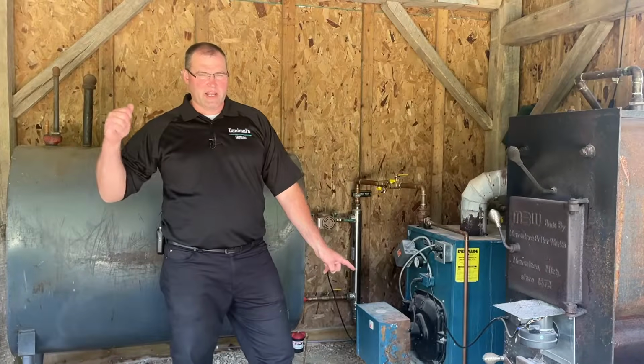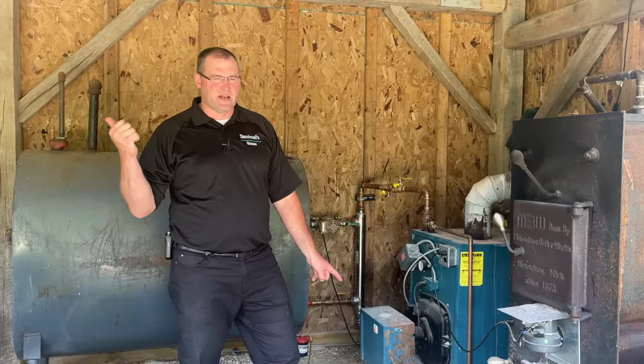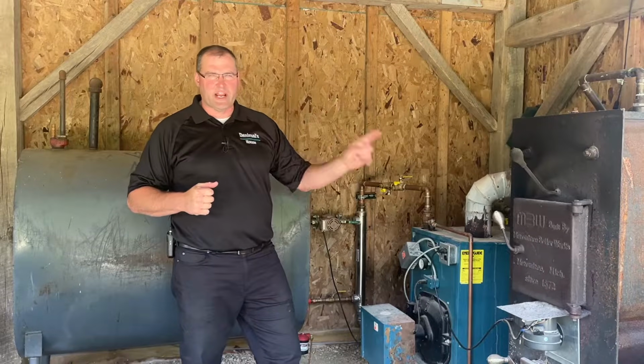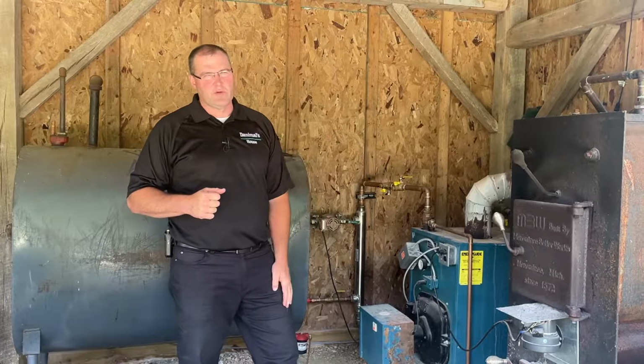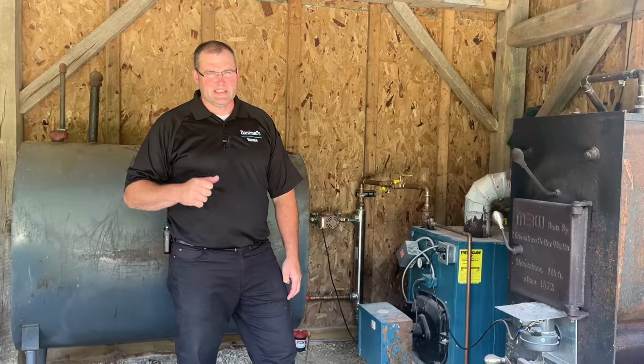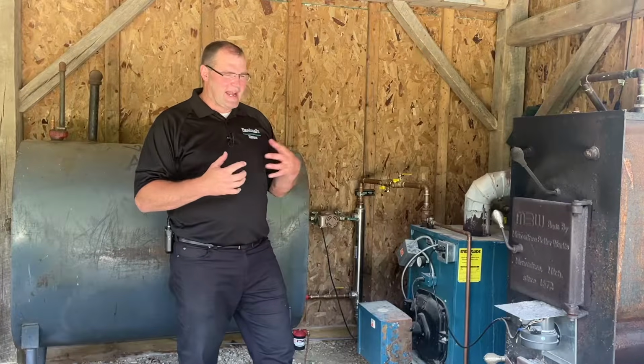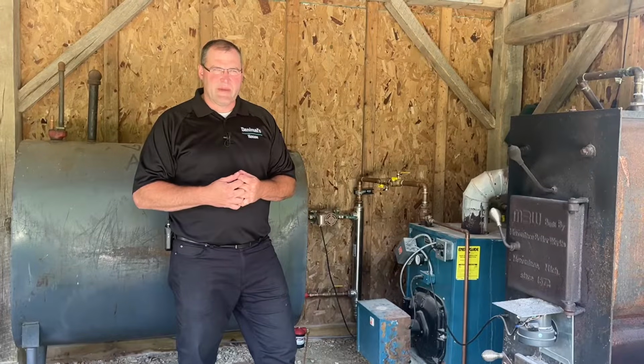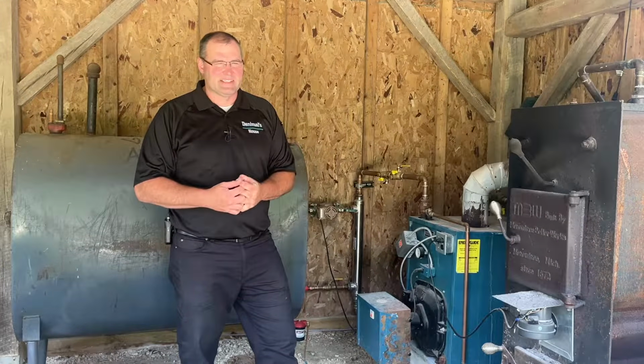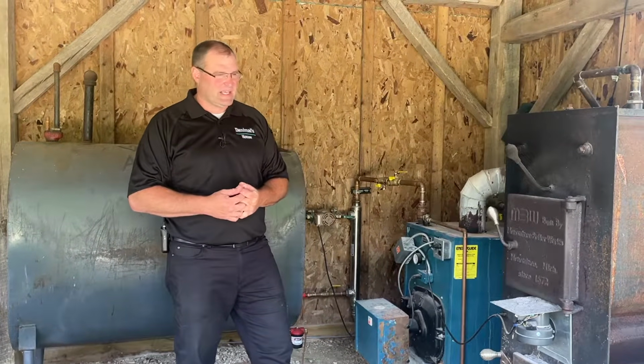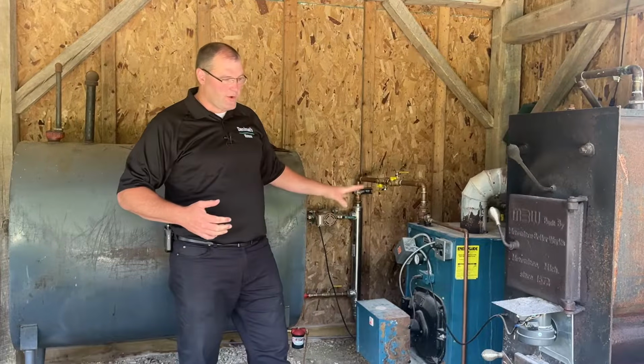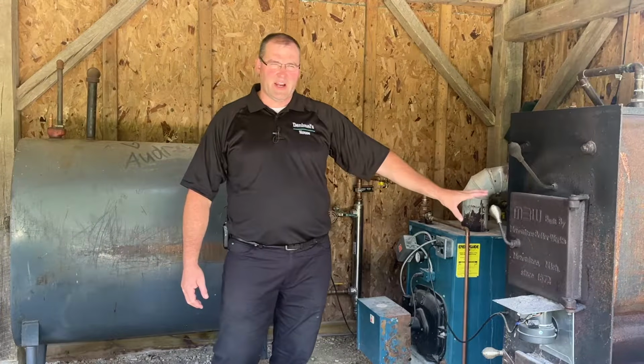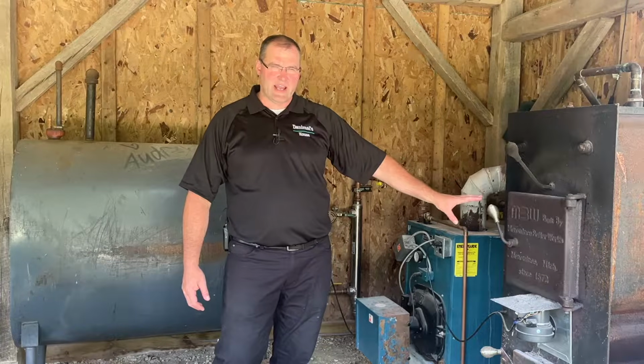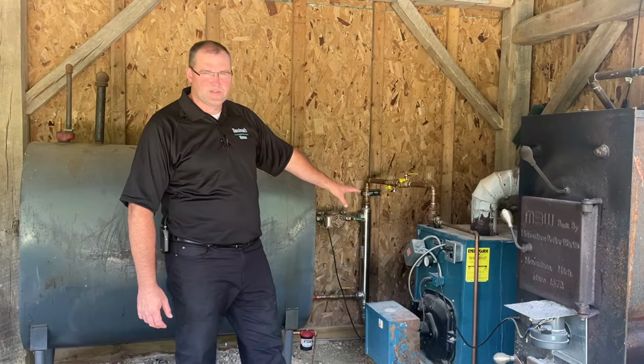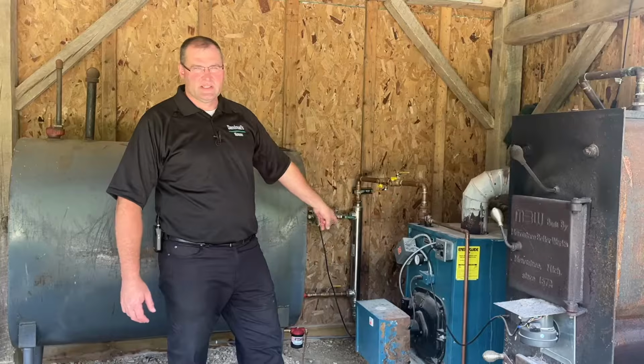If I'm running my equipment properly, there's enough flow where even if I have a raging fire in here, I can't get over 185 as long as I've got enough water flow. So I've got those capabilities matched so the system can't destroy itself easily. They work really well together. When the fire gets low and it's time to fire up, this compensates for it, and when that fire is going good, this shuts off.